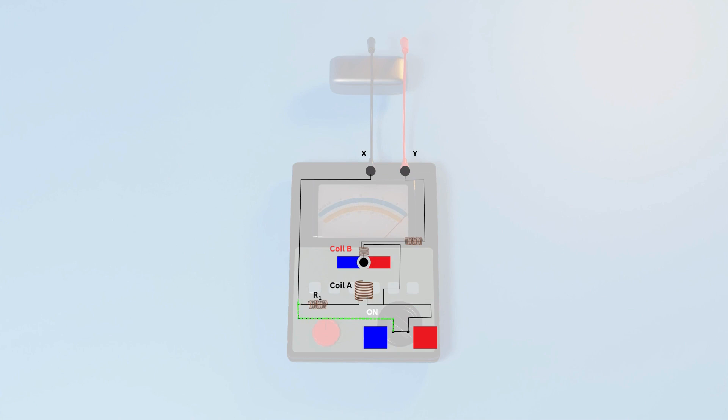While testing, the terminals X and Y are connected across the terminal and body of the machine for measurement. Now, the current passes through the deflecting coil B. The deflecting torque produced by coil B interacts with the torque of coil A and rotates the moving element to indicate the resistance value.